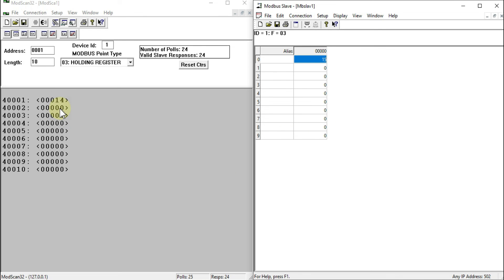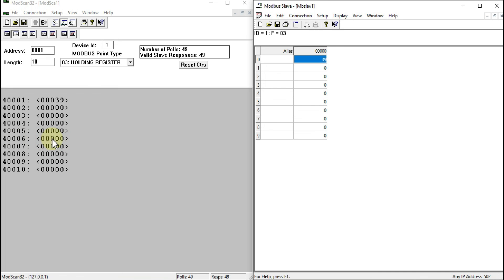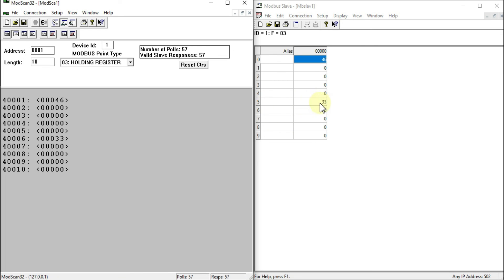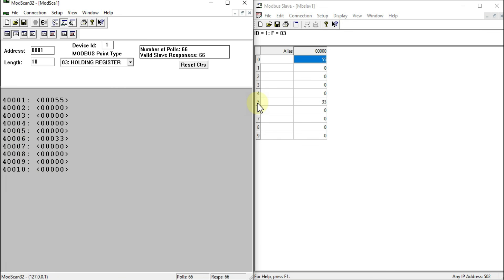I can also update holding register values from the client. If you connect Modbus Slave to any SCADA system, you can update holding register values from that SCADA system too. For example, using ModScan32 as the client, if I update register 40006 to the value 33 and click Update, the value updates on the server. Note that address 0 corresponds to 40001 and address 9 corresponds to 40010, so 40006 corresponds to index 5 here.